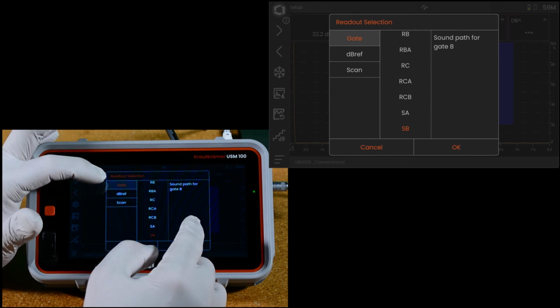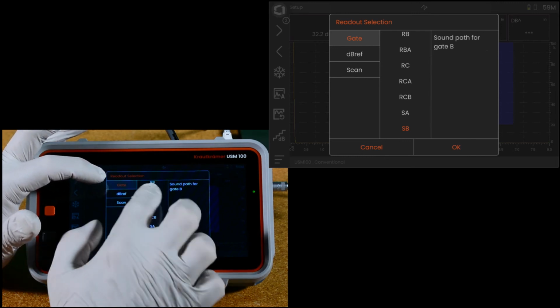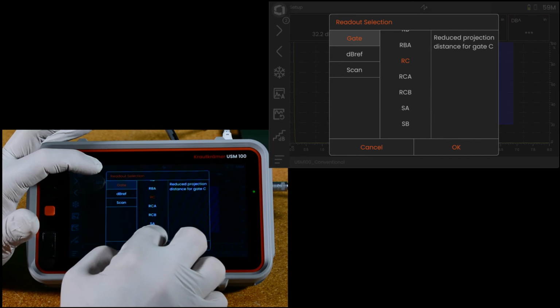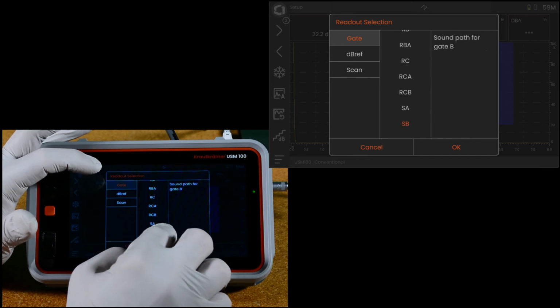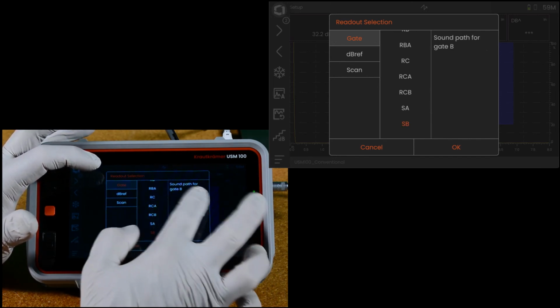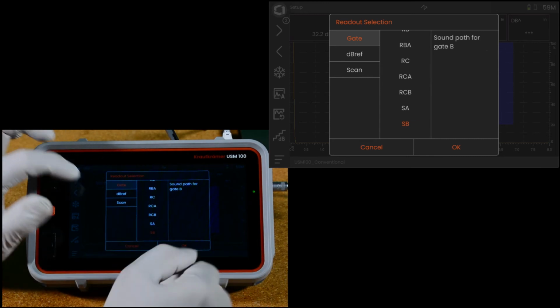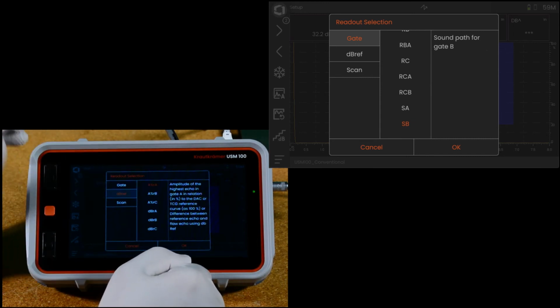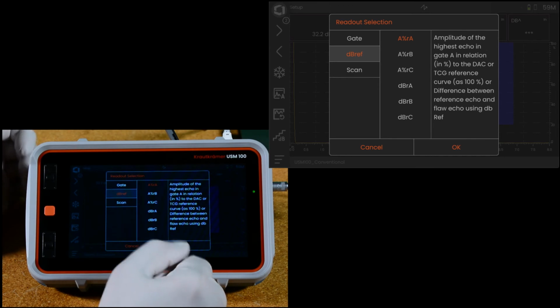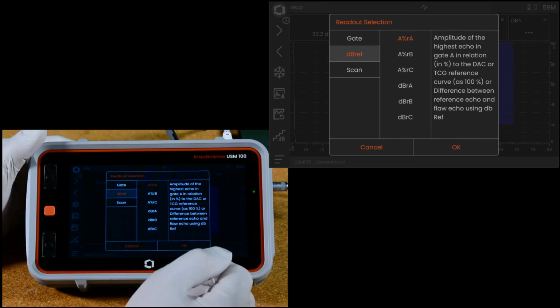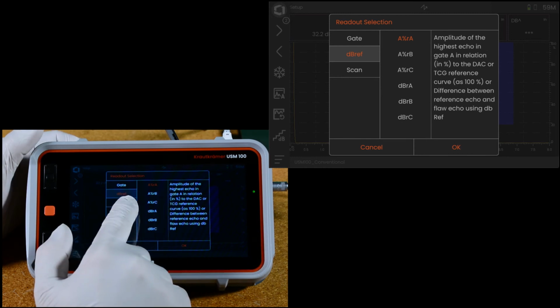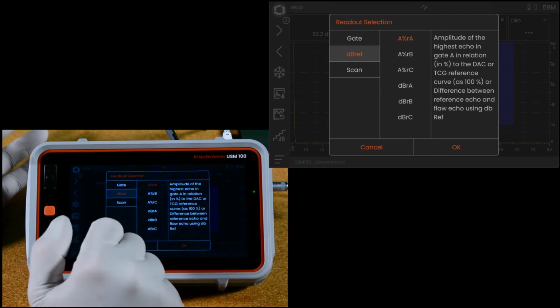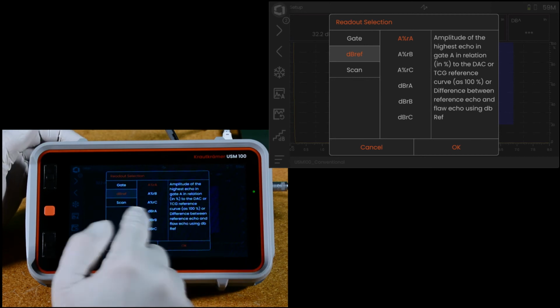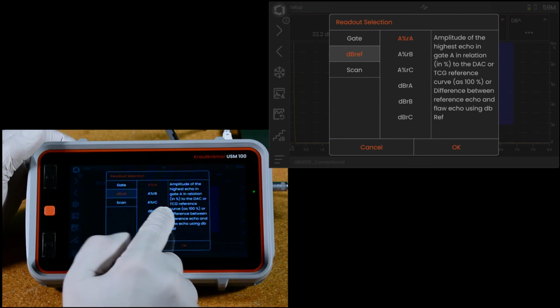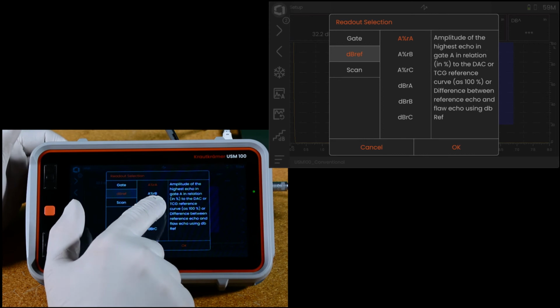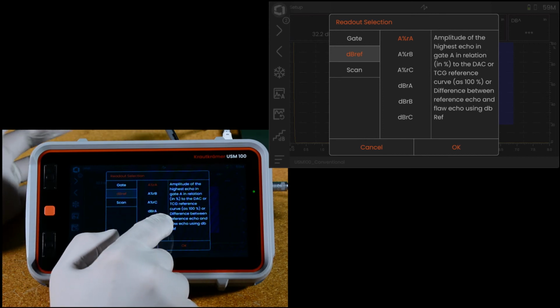Inside the selector, the top choice is always one of the gate readouts. And you see we already had SB selected, sound path for gate B, so we get an explanation of what each of these means. Right below gates is whatever evaluation mode we have chosen for the instrument. Right now this one's selected as dB ref. That is context sensitive to the selected evaluation mode. So we can look in a minute and see how that changes. But again, you have just the readouts relevant to the chosen evaluation mode.